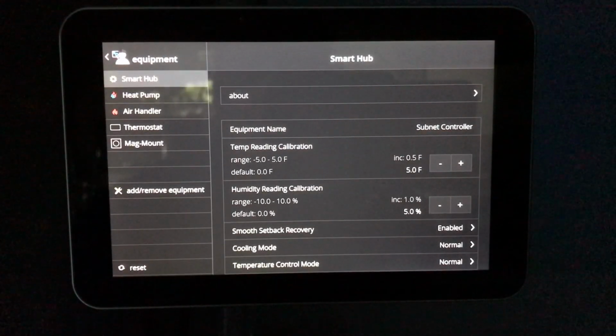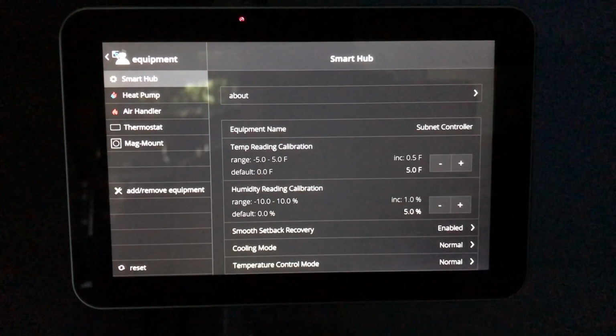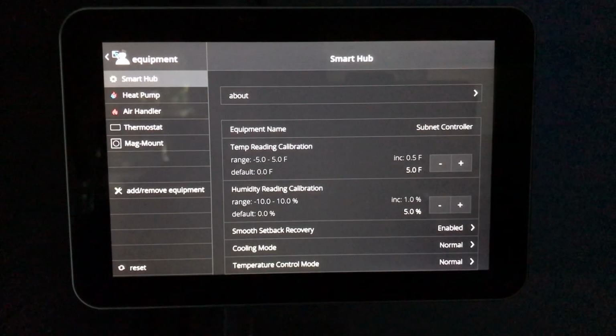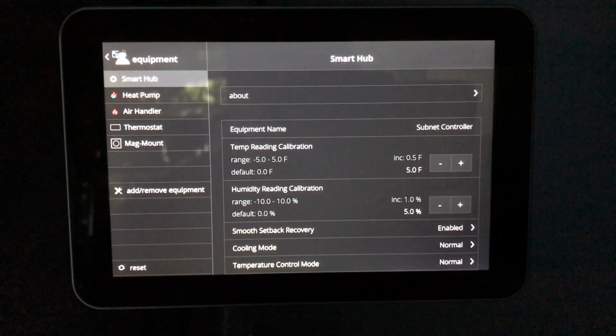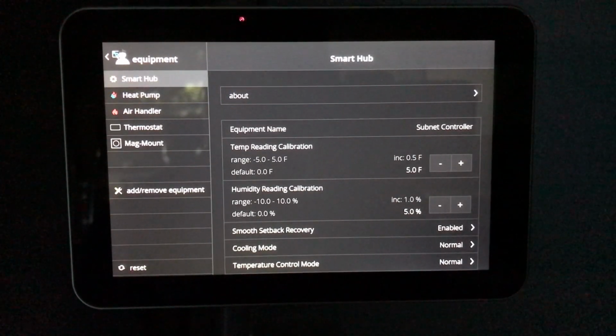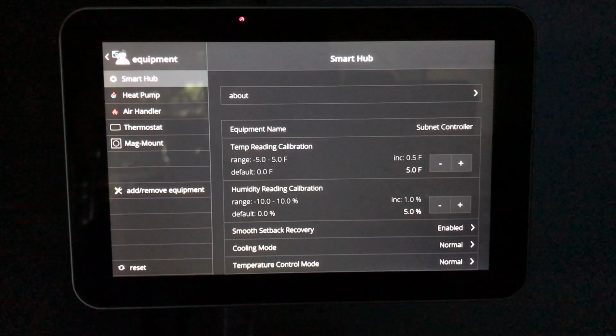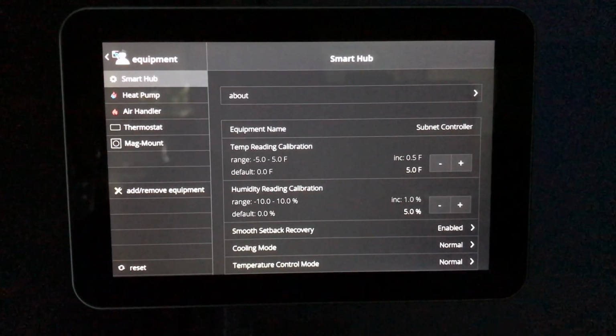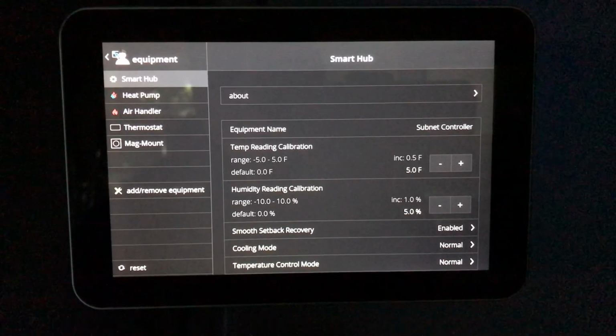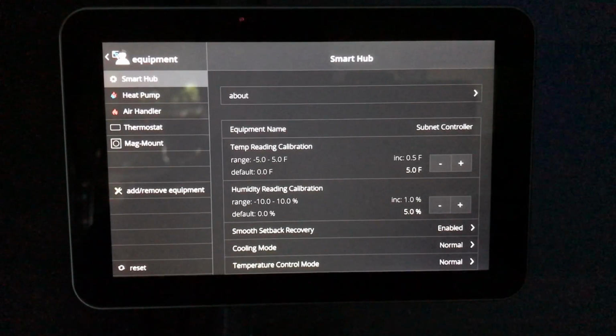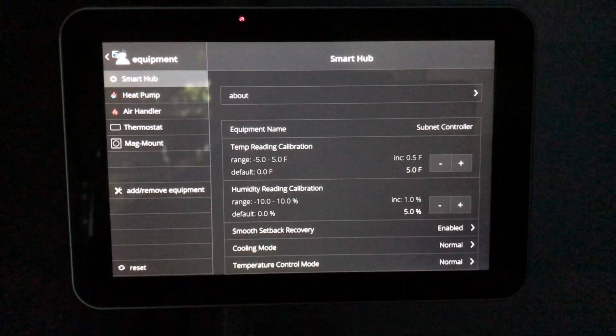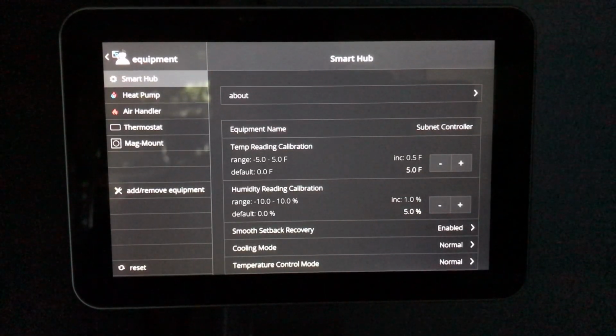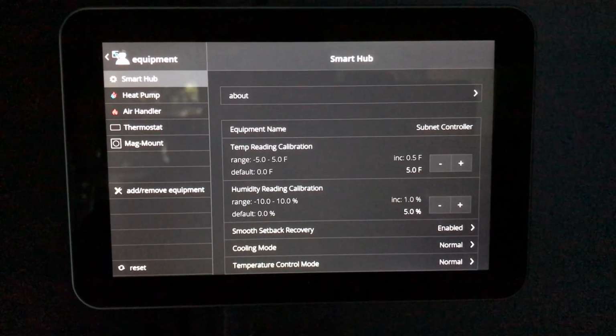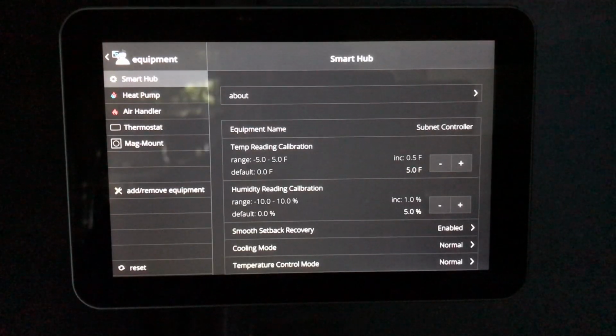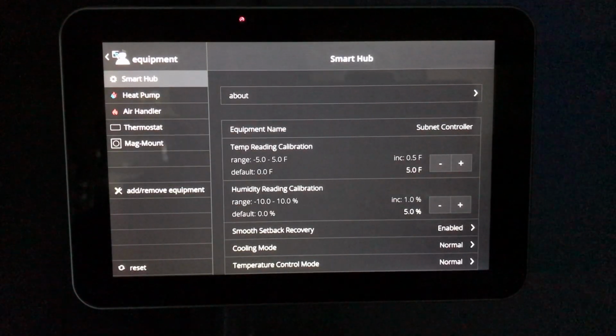And now I just want to preface it with this: you're only going to know what to calibrate it to as long as you're using a very accurate psychrometer. So you probably don't want to just change these based off of how it may feel, without having the exact data. And again, my experience with some of the most accurate psychrometers is it usually takes at least a good 10 to 15 minutes to really dial in the exact temperature and humidity, especially where the thermostat is located. So make sure you give it enough time.